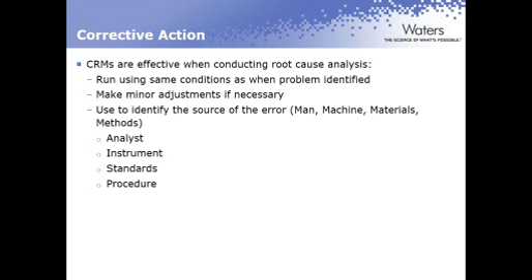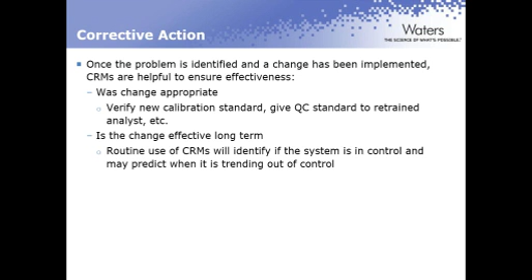Okay? So then we go into the implementation of the correction. Once that problem's identified and change has been implemented, you can use your CRMs to help ensure the effectiveness of it. Was that change appropriate? Okay. We make sure that we have a new calibration standard to verify. Did we have to retrain the analyst? Give them the CRM to test that they've been retrained properly. Okay. Then the monitoring part comes in to make sure that the change that we made is effective long term. And again, we can have routine use of our CRMs to do that. Continue the control charting so that we can look at trending to see if anything's going out of control.